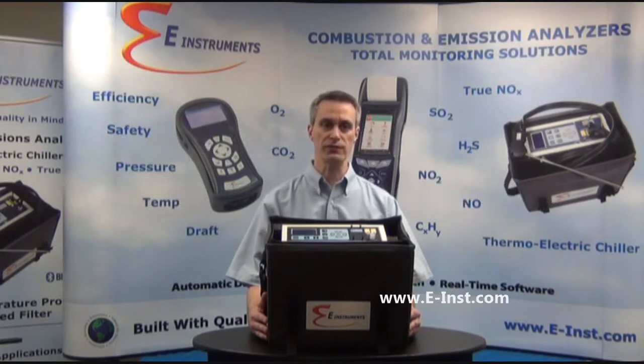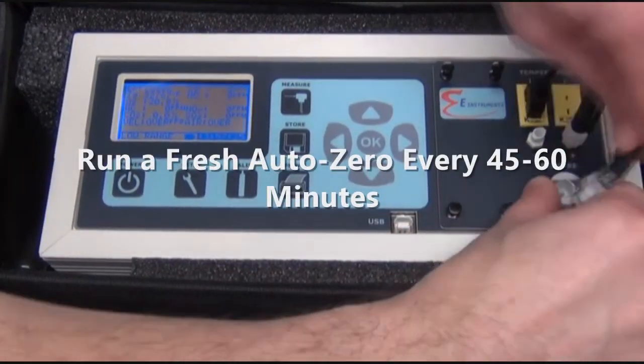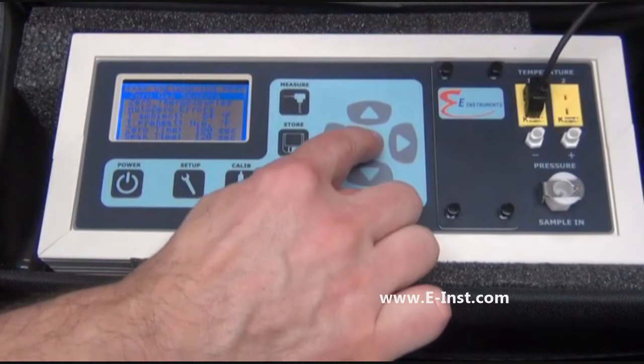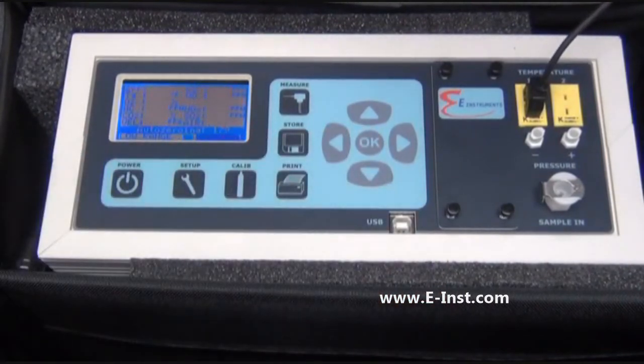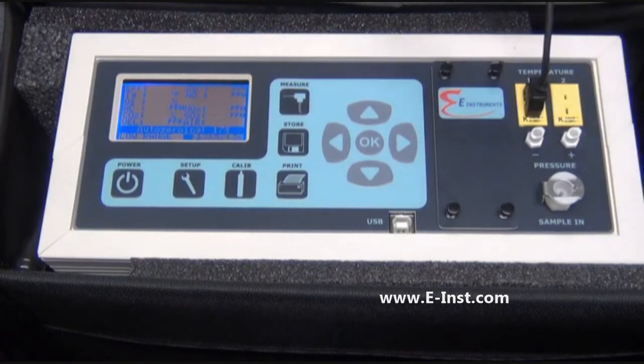If you have the analyzer running for more than 45 minutes at a time, it is recommended to run a fresh auto zero cycle every 45 to 60 minutes by disconnecting the hoses from the analyzer and using the calibration button menu to force the calibration. This periodic purge will help prevent sensor drift and optimize the accuracy of the gas sensor measurements.